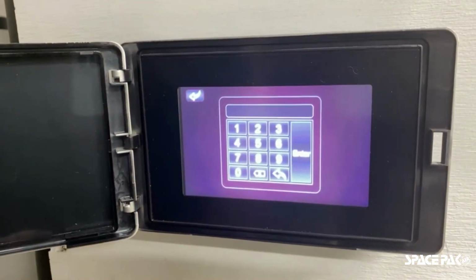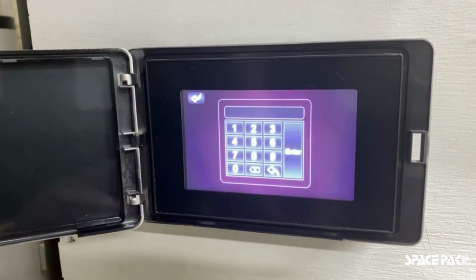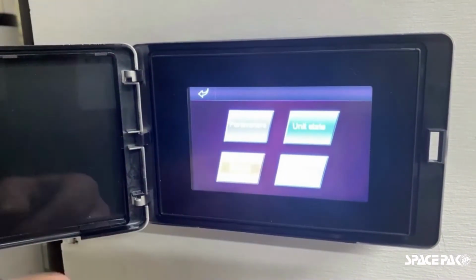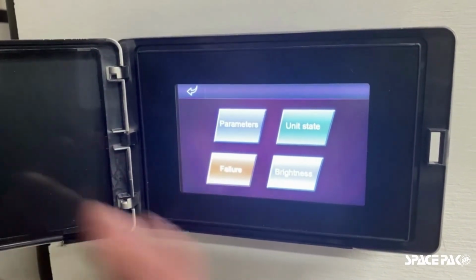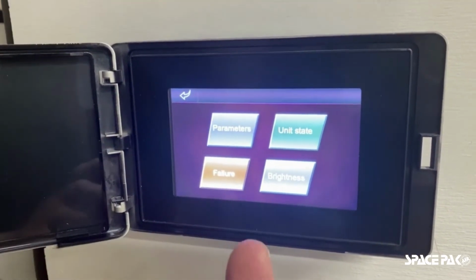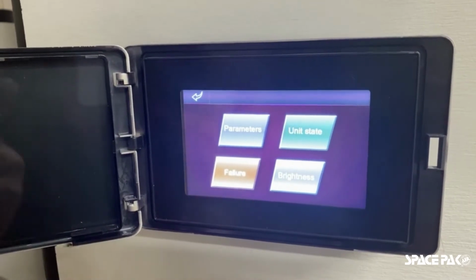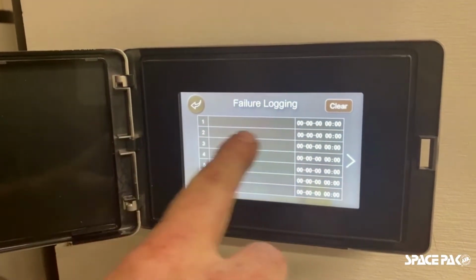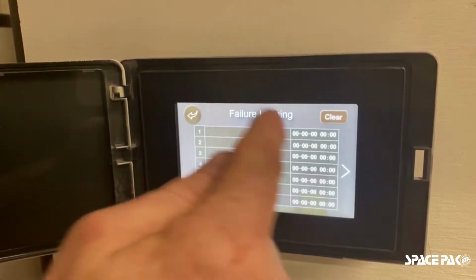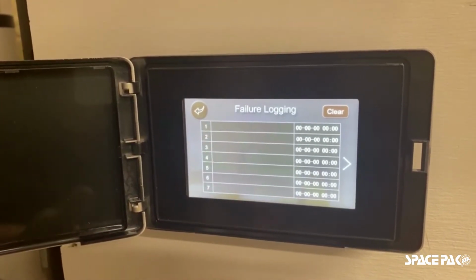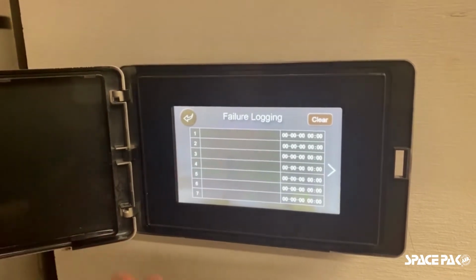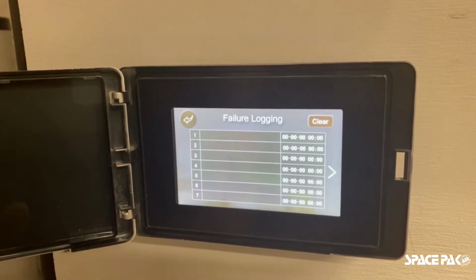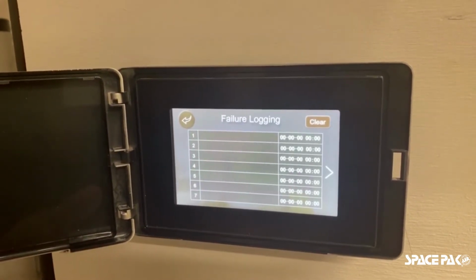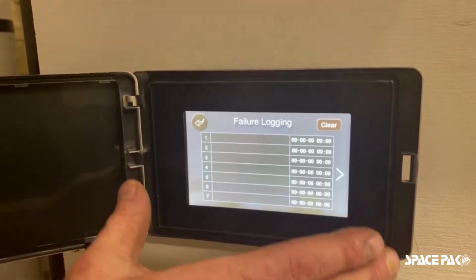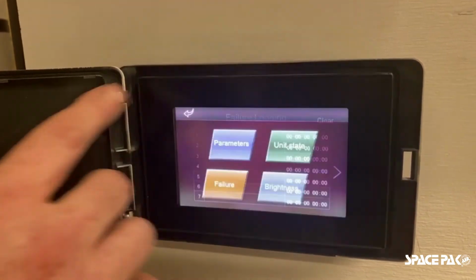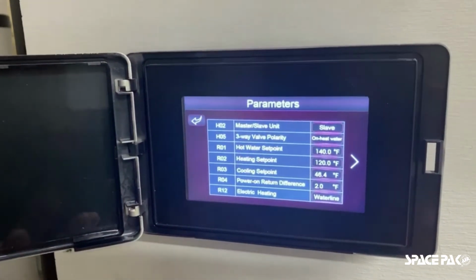Now, if we were to go into our factory settings, the factory setting that you're going to want to access would be factory setting number 22. Press enter. Now we get into the parameters, we get into unit state, brightness, and then if there was ever to be a fault, we'll just jump right to that. Now, if there was ever to be a fault, the most common fault being something associated with flow, we would press this button and it would show right here very clearly there was a flow fault on this date at this time. Okay, now flow faults can be automatically corrected. Potentially even an airbound system which might have adequate flow but then drop the amount of flow and then could return to flow, right? If that air blockage has kind of moved down the line, it would still show you that there was a failure and it will log it for you. Now, if we were to go straight into the parameters, we know we have a cooling call right now.